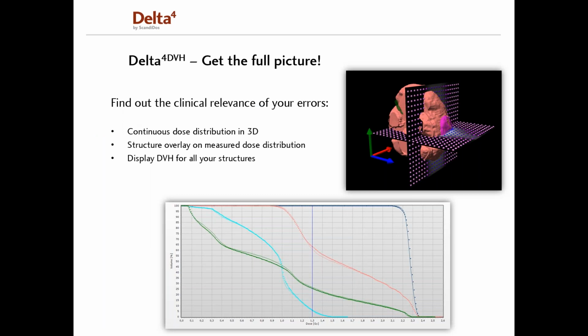With the Delta4 DVH, you can calculate 3D dose distributions within the Phantom geometry using your measured values. So this is independent from the treatment planning system. The dose distributions are calculated using ray tracing technology, and the results will be instantly available after you finish your measurement. The Delta4 DVH also allows you to overlay the structures outlined during the treatment planning onto your dose distribution and to display dose volume histograms inside all of these structures.